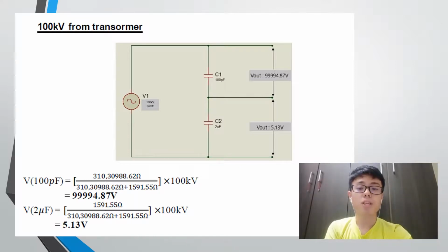For the specification of the measuring capacitance and secondary capacitance, the maximum voltage of the measuring capacitance is 100 kV, while the secondary capacitance is only 7 volt RMS. All the capacitors and the measuring probe are still in safe condition when using 100 kV and 220 volt.